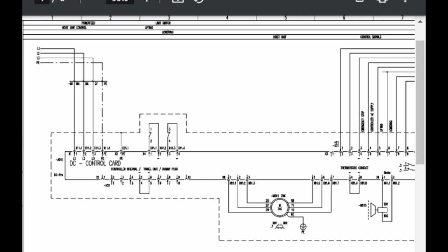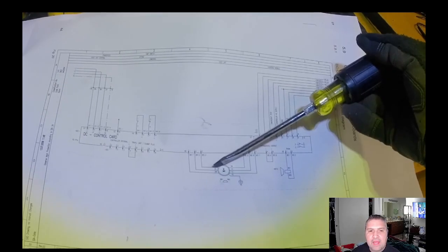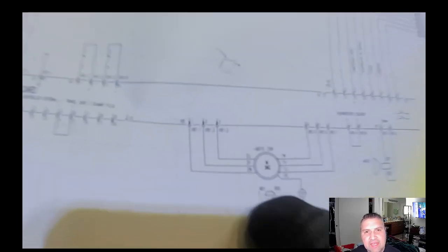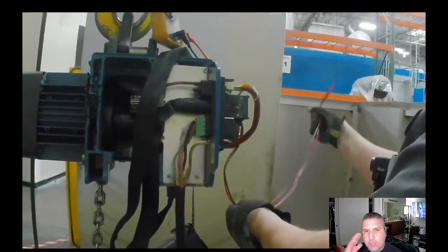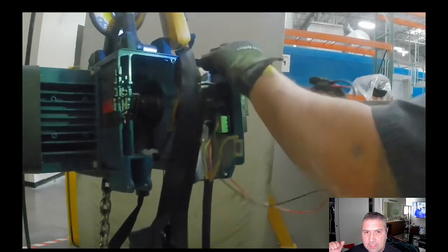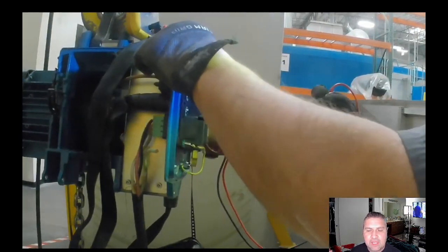Yeah, so this is kind of what I'm looking at right there. You can see I'm gonna troubleshoot these three, and then I'll troubleshoot these three, and then see if I have any variations at that point, because that's the last current supply that goes directly to the motor, and I want to see what both sides are doing. So I had an inclination that one side was solid and the other was not, the side that was faulting out.